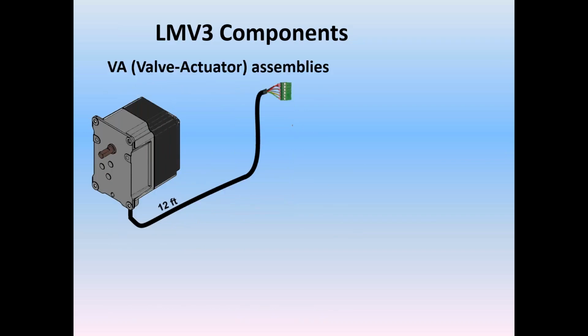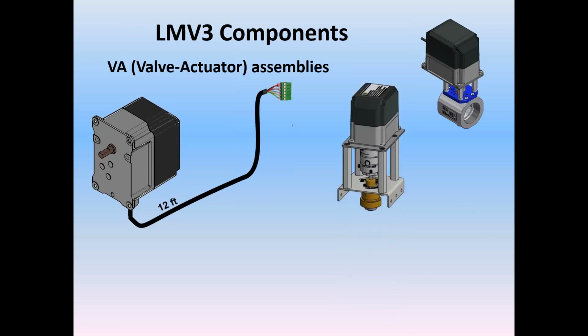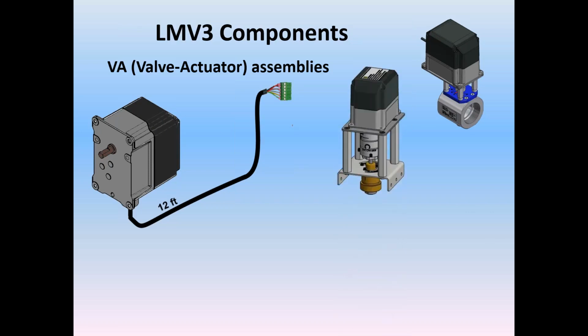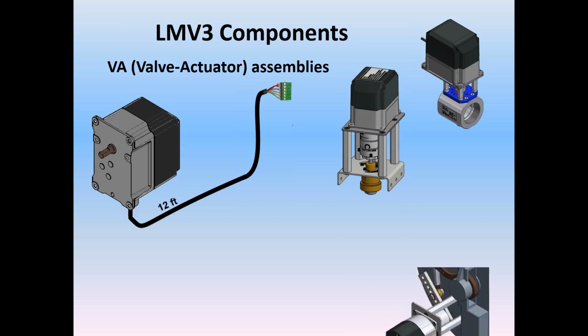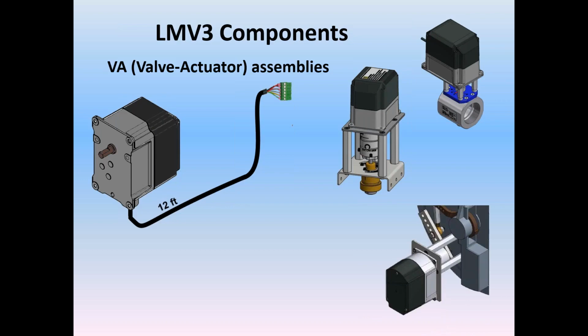The SQM33 raw motor can be used in addition to devices such as a VKG gas butterfly assembly. These we call VA, valve actuator assemblies. It's the servo motor plus the device on the other end. It might be an oil controller, such as a Hauck oil valve with brackets, couplings, and standoffs, as you see illustrated. It might be a particular OEM, like a rotary air damper on a Cleaver Brooks boiler.